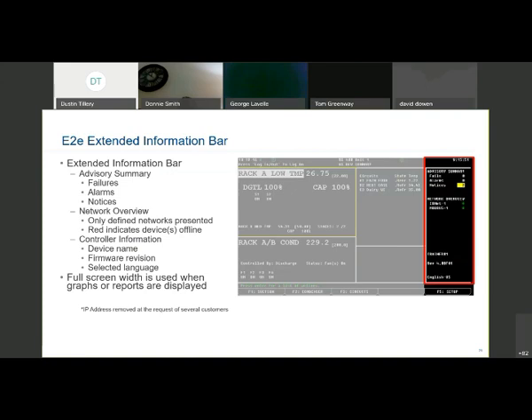If we have devices out there that are BACnet devices, but we have not yet told the E2 that they are present, it will not show up here. This is good for quick glances at your communications. If you have a green dot, everything on that communication loop is communicating back to the E2. If that dot is red, there is a device on that loop that is offline.